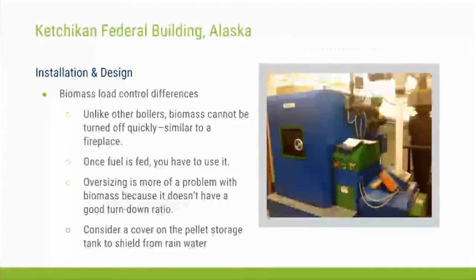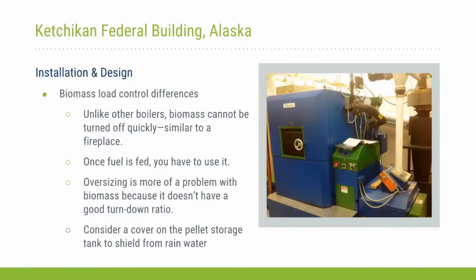One major factor that you have to consider with biomass boilers is that their control is a little bit different from conventional boilers that we're familiar with. Natural gas boilers or fuel oil boilers are a lot easier to control, meaning that you can modulate the heat output fairly easily by modulating input fuel. In terms of a biomass boiler, you cannot adjust the heat output as easily as you could with other types of fuel boilers. And that's essentially the crux of operating this kind of system. When you feed the fuel into it, you cannot take it back. You have to use it.